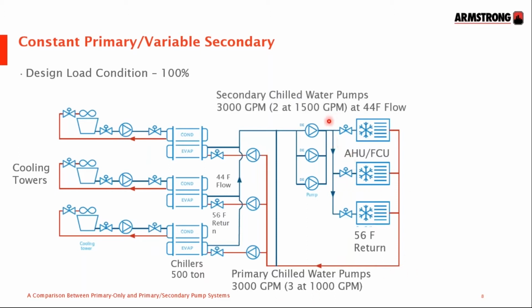are sized for 50% duty, 50%, and then 50% standby. In this particular case, two pumps running at 1500 gallons a minute at full flow will then take the 3000 gallons a minute out of the primary side and pump it through the secondary side through the air handling units, where they're warmed up and back to the system. Because there's 3000 here and 3000 there, there's nothing going through the mixing header here. And at 3000, of course, at full load, the chillers are operating at peak efficiency because they're constant speed chillers.